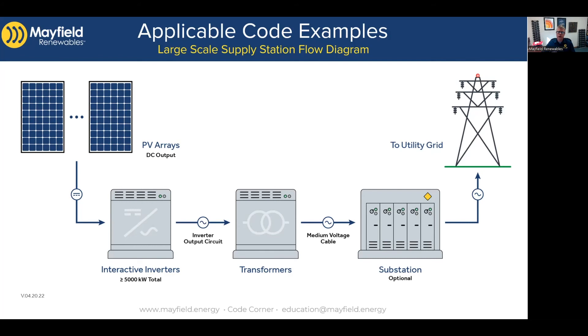Section 691.8 talks about the maximum system voltage, and again it refers back to the engineered design — we use an engineered design to calculate that maximum system voltage. Section 691.9 covers the disconnection or isolation means. Notably, the disconnect or isolation means doesn't have to be integral with the equipment — it can be remote. Of course, it needs to be documented, pointing back to 691.6.